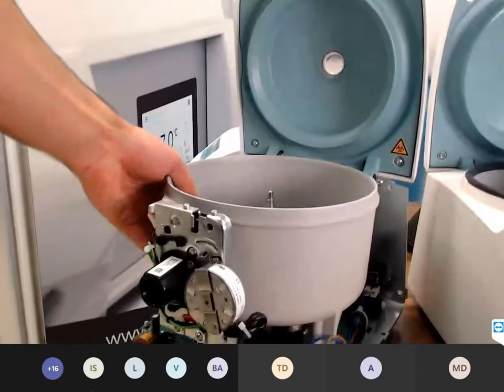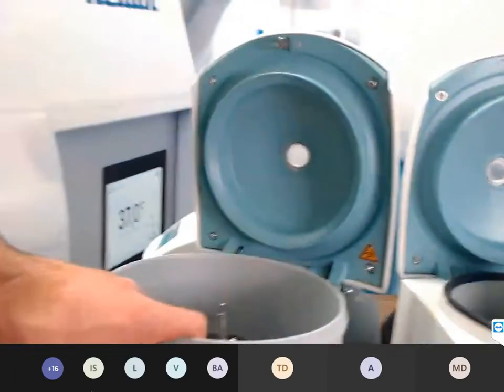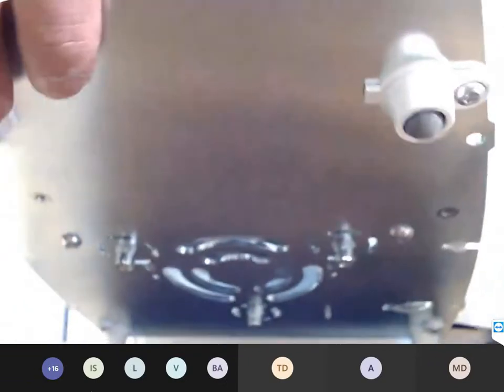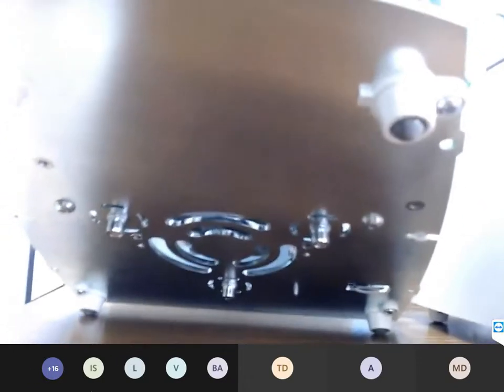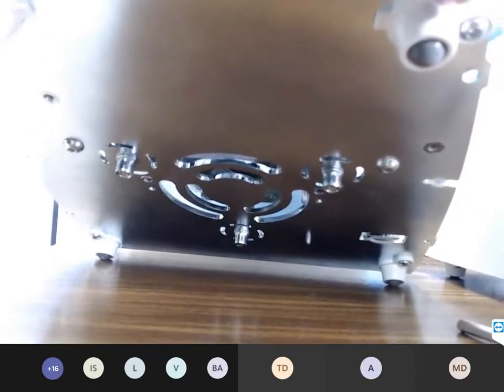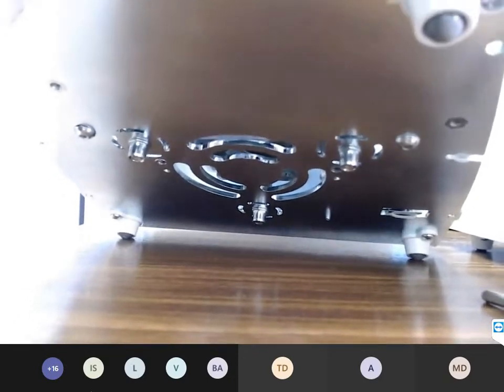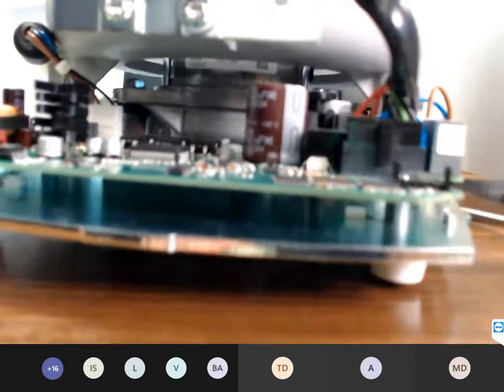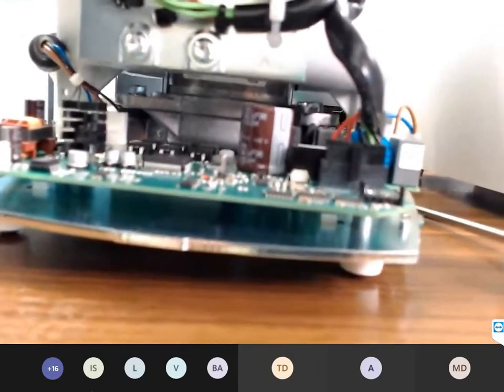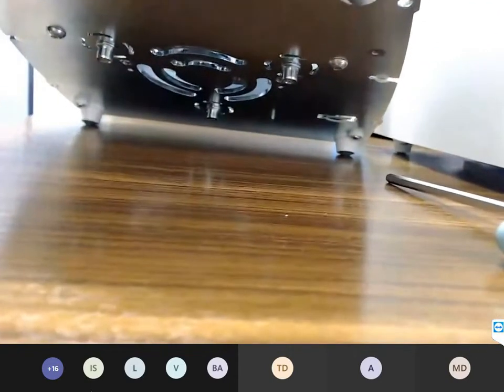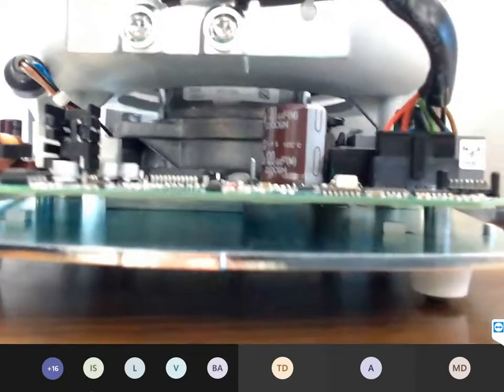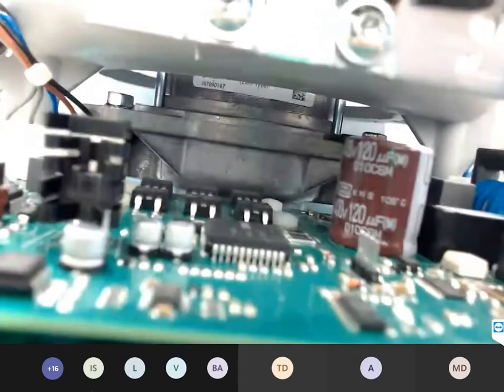The reason for the destroying of the Hall sensor is the customer holds the device in case of a vibration. But they don't need to, because we have here on the bottom rubber feet. This is not only a foot, that's a rubber foot. In case of a vibration, the rubber feet take the vibration and hold the device stable. All customers hold the device, that's not good. If you hold the device, the vibration cannot go to the rubber feet. The force cannot go, and then we have a maximum imbalance here, and that's the reason for the destroying of the Hall sensor.